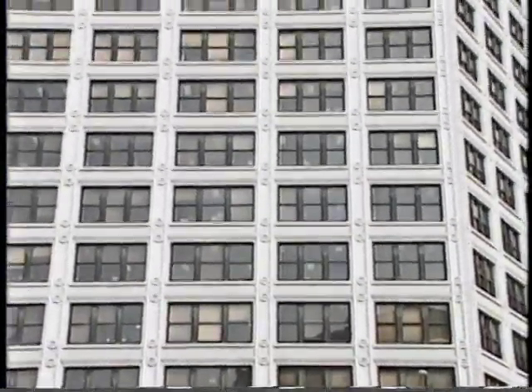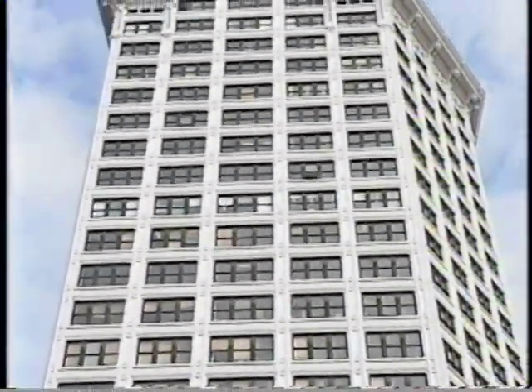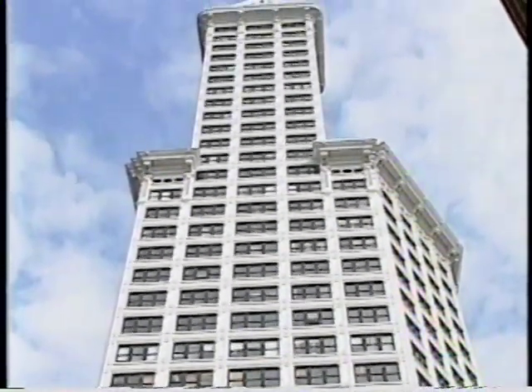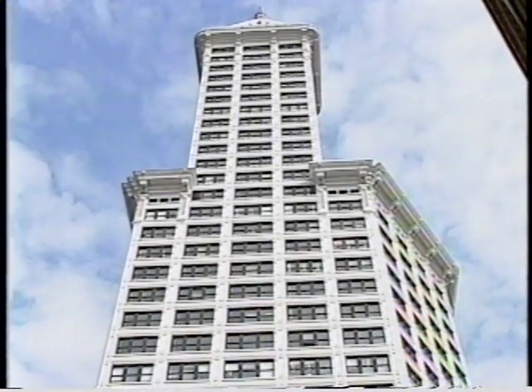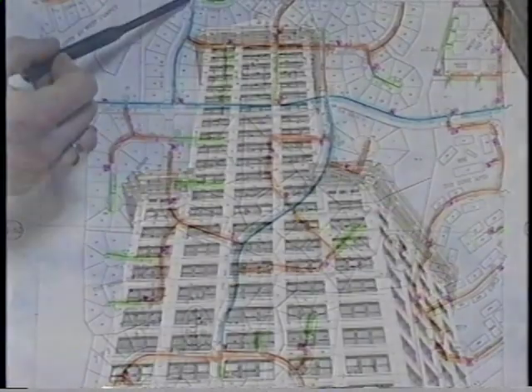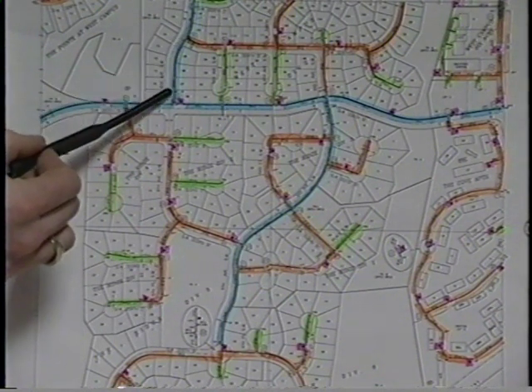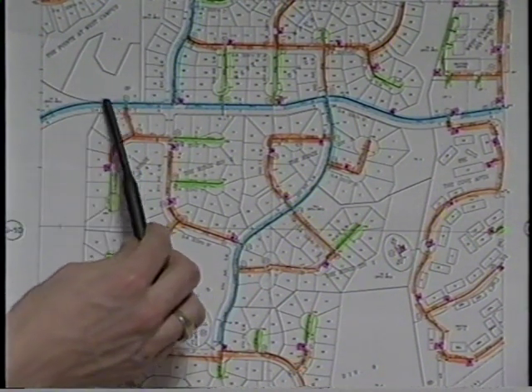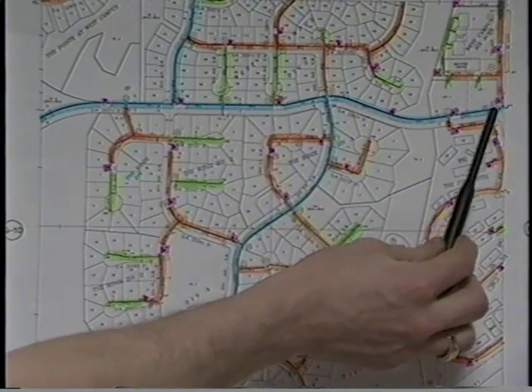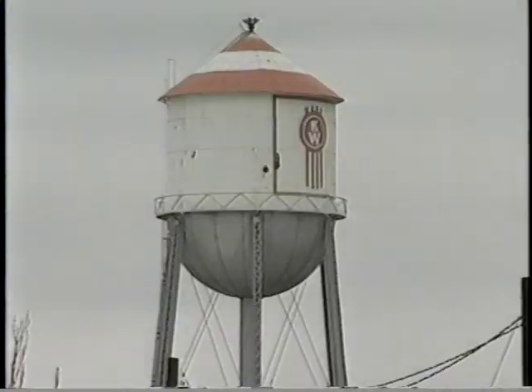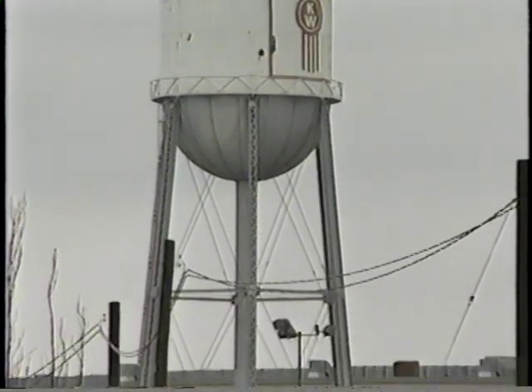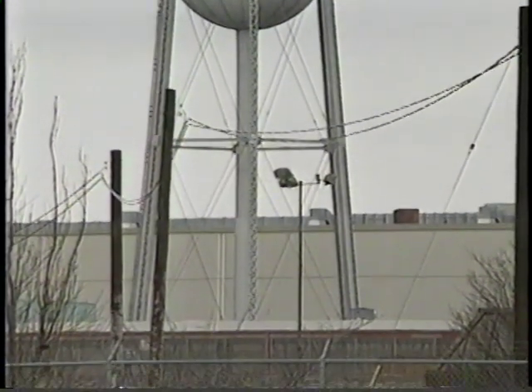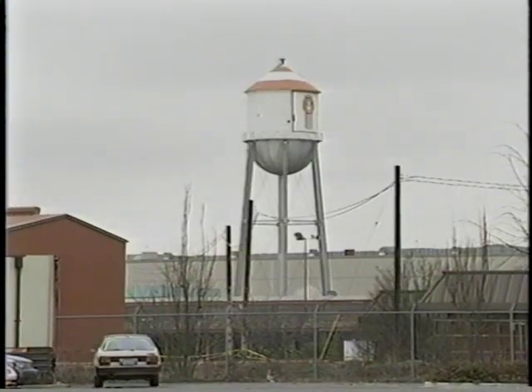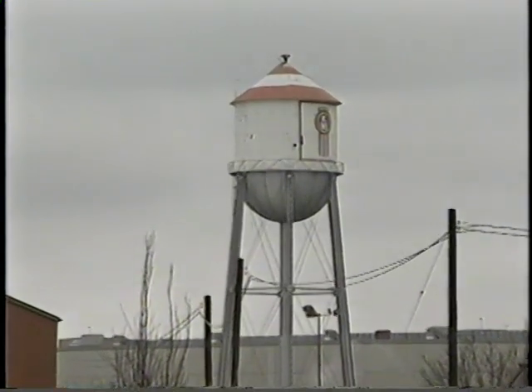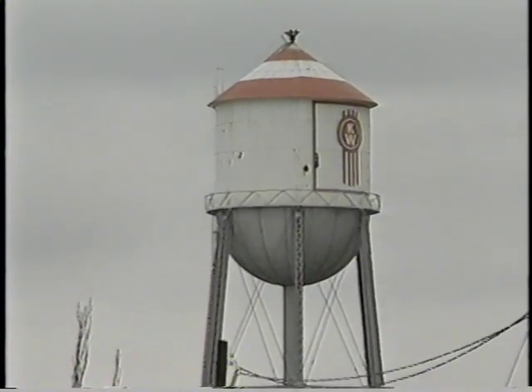A minimum water supply must be able to deliver the required volume of water to the highest sprinkler in a building at a residual pressure of 15 pounds per square inch or 100 kilopascals. A connection to a public water system that has adequate volume, pressure, and reliability is a good source of water for automatic sprinklers. A gravity tank of the proper size also makes a reliable primary water supply source. In order to give the minimum required pressure, the bottom of the tank should be at least 35 feet above the highest sprinkler in the building.